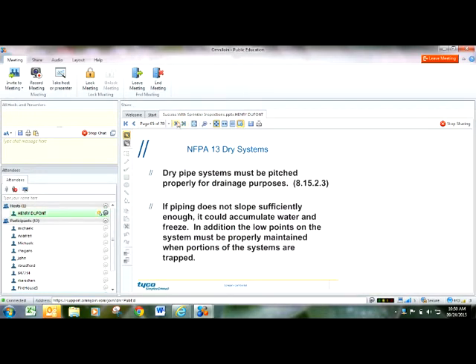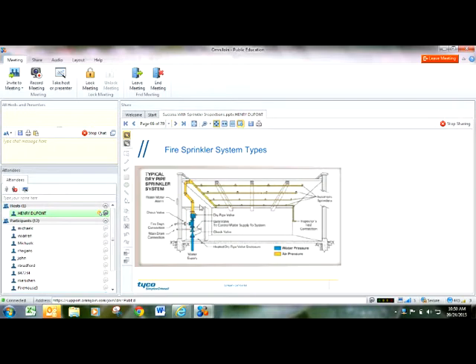We talked about this a little while ago. Dry pipe sprinkler systems have to have pitch on them. So this is a dry pipe sprinkler system. All the water that could be in these lines has got to be able to drain. So it should be pitching backwards to this cross main. This cross main is pitching backwards to the riser and this drain.